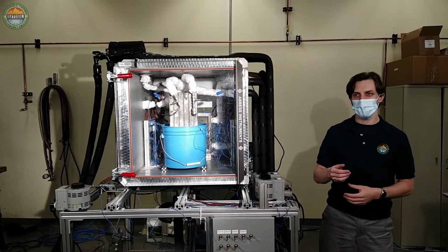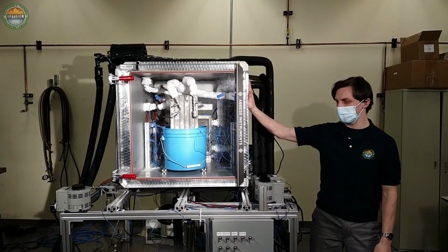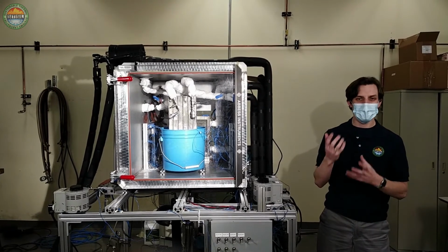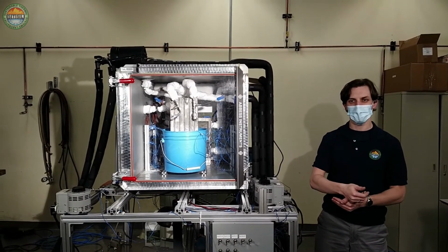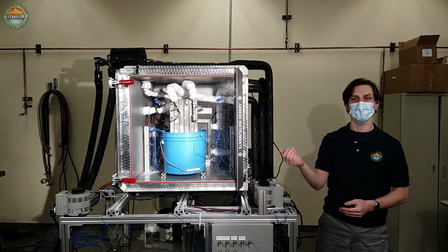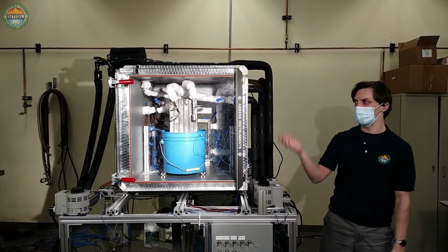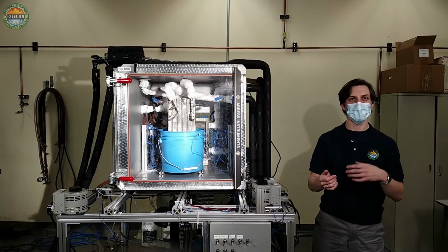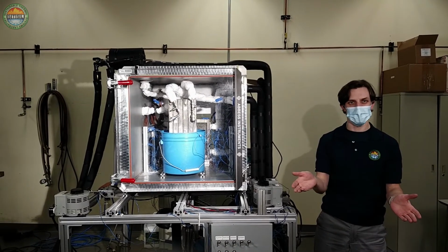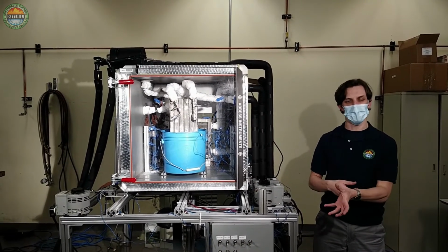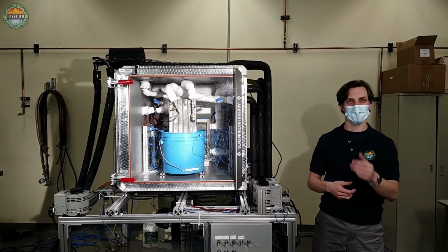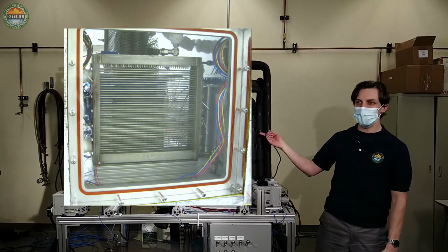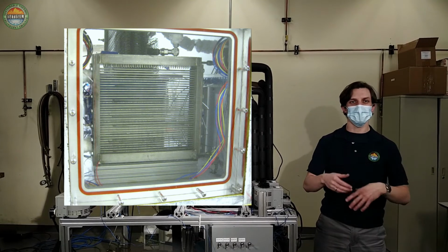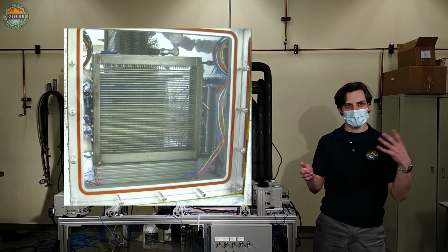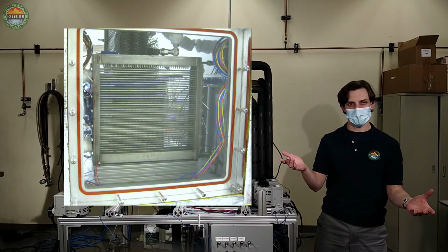Right now we're using this test stand to test and really prove the concept that we can do water purification and space conditioning with an absorption heat pump. The heat exchanger in the front is our prototype evaporator and condenser, operating as an evaporator in low pressure mode and a condenser in high pressure mode. The heat exchanger in the back is a prototype absorber and desorber, again absorber in low pressure mode and desorber in high pressure mode.